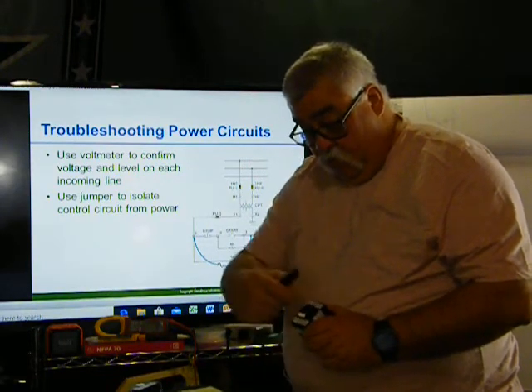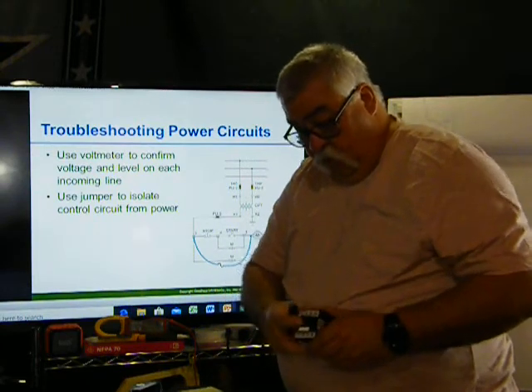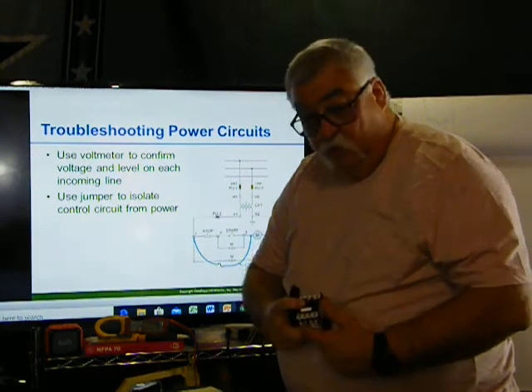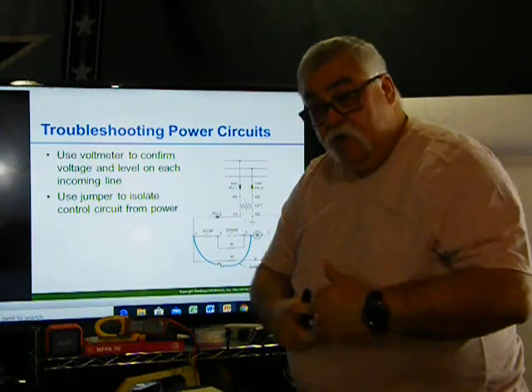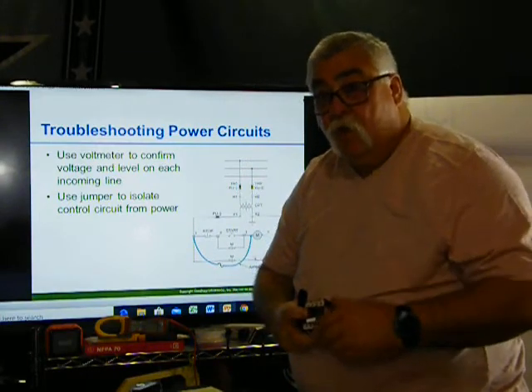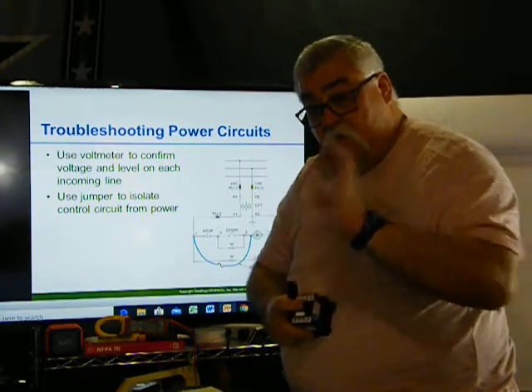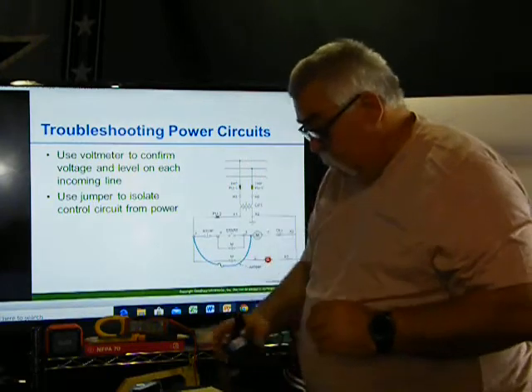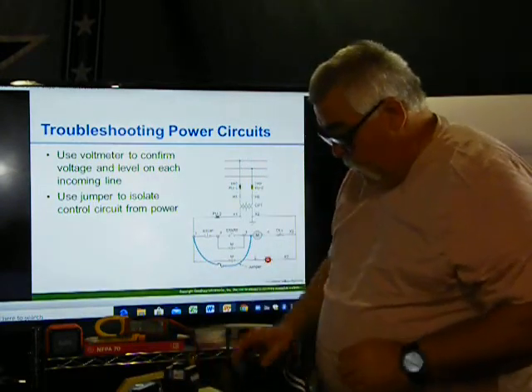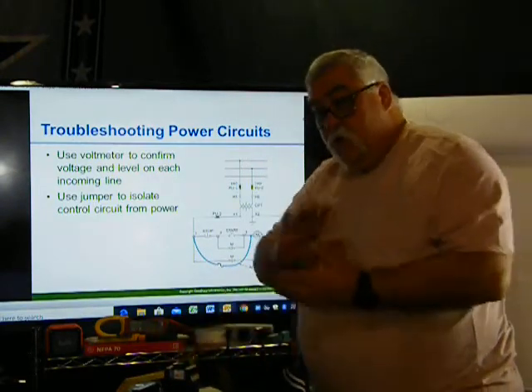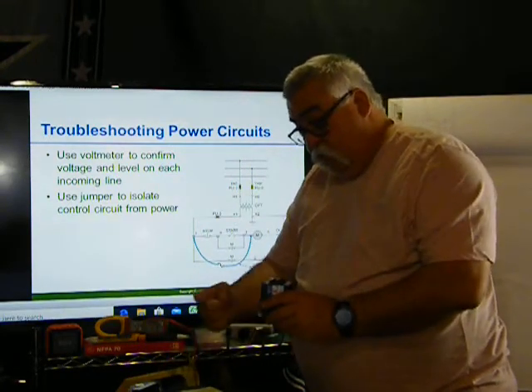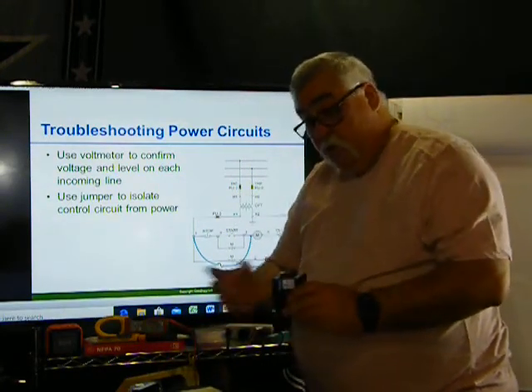If you close this, you have voltage on top, but no voltage at the bottom, that means your contactor's insides are gone. So it's not making contact. As it closes, it's not making contact. As this closes, the contacts are not making contact, so I don't have voltage coming out here. I have voltage coming here, but I don't have it coming out here.